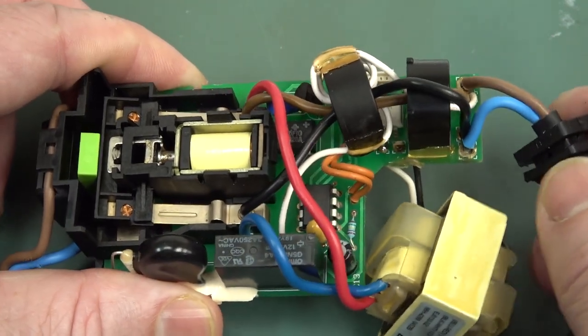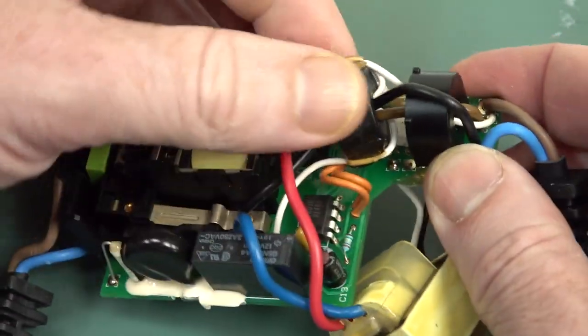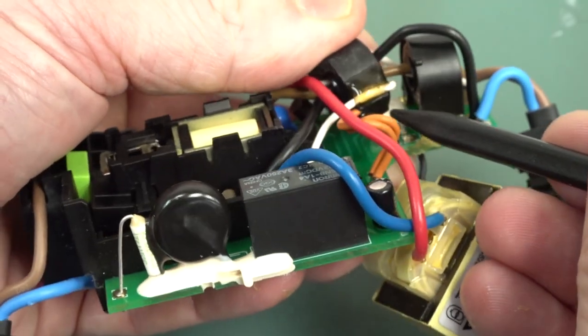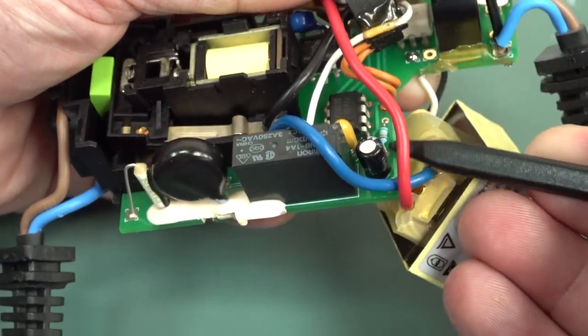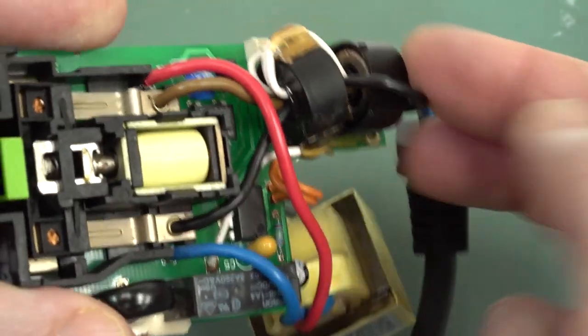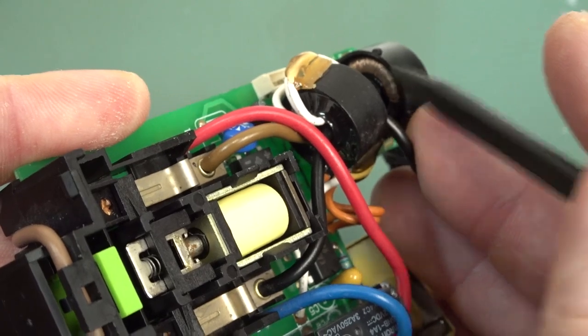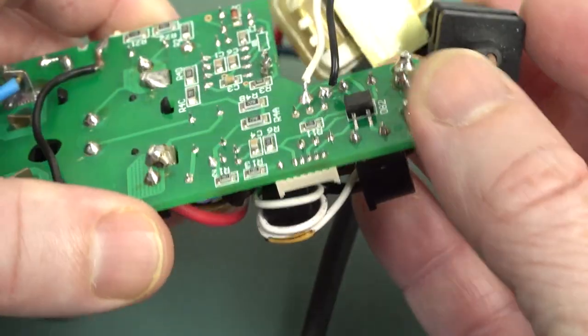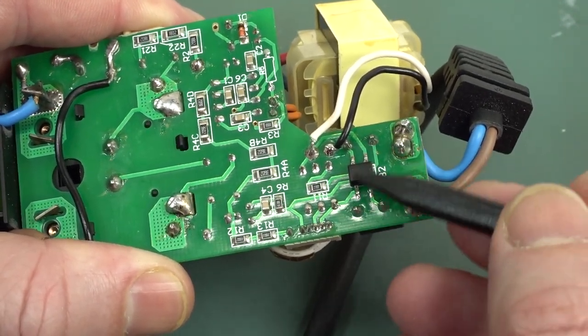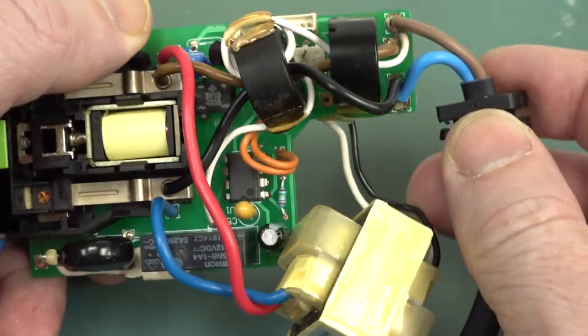Taking off that plastic cover — look, they're breaking both the active and the neutral there. Unbelievable. The amount of complexity they've gone into doing that. There's a little solenoid in there, and it looks like they've got a low voltage transformer here for powering various stuff. They would have got that right with all the requisite approvals — they would have been very careful with everything in this thing because they didn't want to screw it up. Anyway, let's have a look at how they're actually doing the current tripping here.